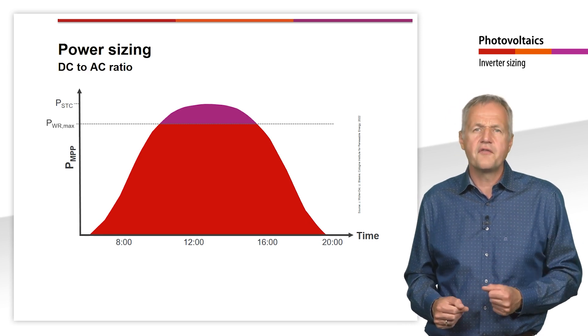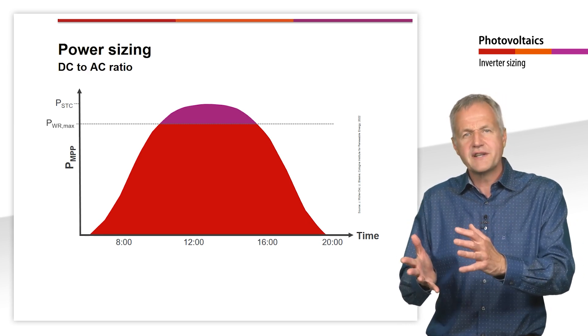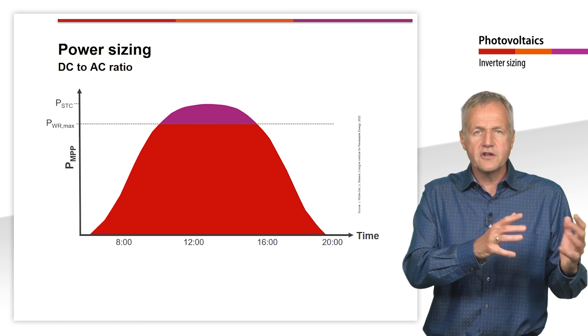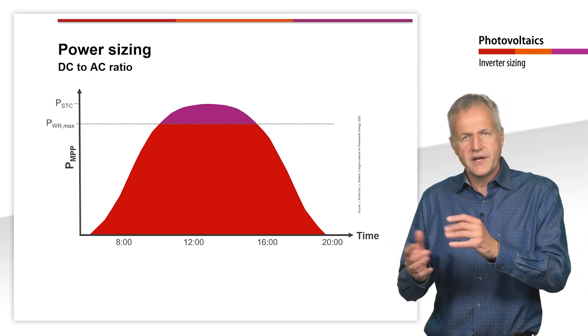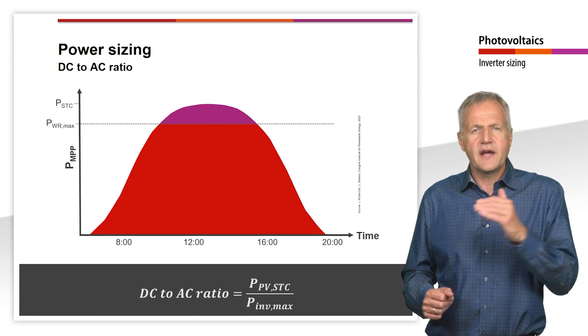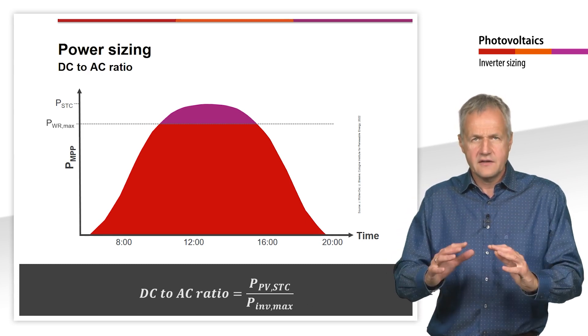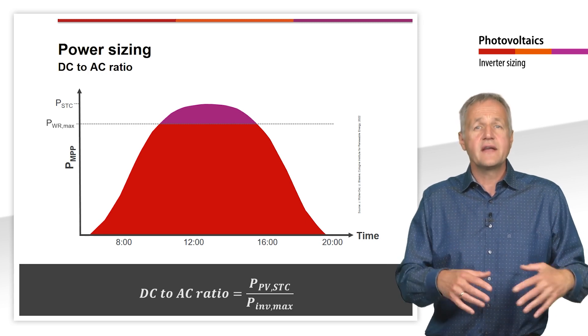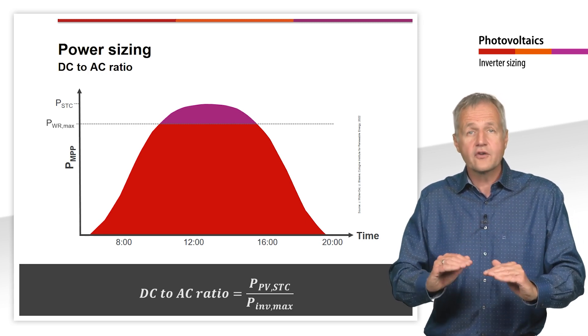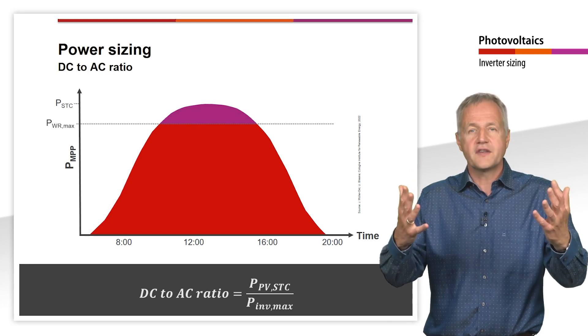The ratio of the nominal power of the solar generator to the inverter is also called the DC to AC ratio. For example, a DC to AC ratio greater than 1 corresponds to an undersized inverter, and a DC to AC ratio smaller than 1 corresponds to an oversized inverter.